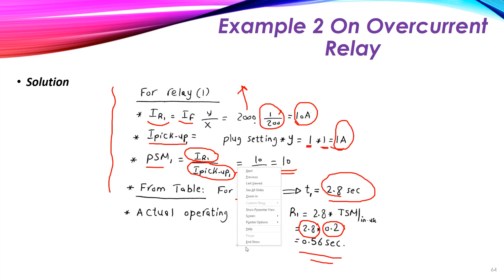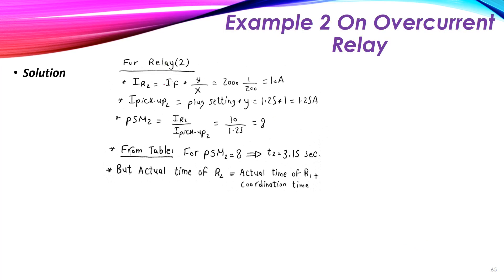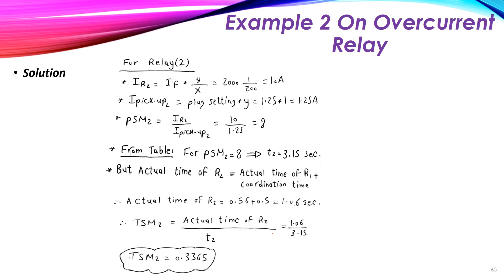What is the time of relay number two? Remember that the time gradient between the two relays is 0.5 seconds. The time of relay number two is equal to 0.56 seconds — the time of relay number one — plus 0.5 seconds, because that is the time margin between them. So the actual time of R2 is equal to 0.56 + 0.5, which equals 1.06 seconds. This is the first requirement.